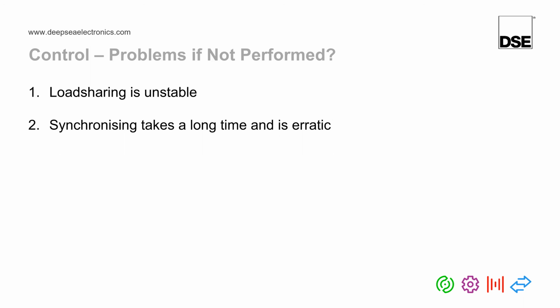But sometimes you may come across a problem where, for some reason, you can't even get within the 75 to 85% window. And this can actually be sometimes caused by settings on the governor and AVR itself. So just taking an AVR I know from memory as an example, if you were to look at the Newage Stamford MX or SX range of AVRs, they do actually have a potentiometer on the AVR known as a trim potentiometer. Now this potentiometer does not set what voltage the generator runs at. Instead, what it does is it sets how sensitive the input on that AVR is.